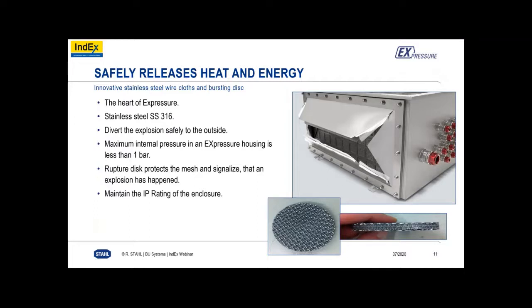So, Gergely, if you wanted to explain that mesh to people, to explain the -33, the EXS that they're unsure of. The mesh is the heart of the ExPressure, and they are flow channels in a multi-layer stainless steel wire mesh system, made of stainless steel SS316, which are welded to the enclosure. As I told before, this mesh diverts the explosion pressure safely to the outside, and the maximum internal pressure in an ExPressure enclosure will be less than 1 bar. The internal pressure increase after explosion is significantly lower than in the conventional EXD enclosure, as I told. And this is what allows us to use lower wall thickness.